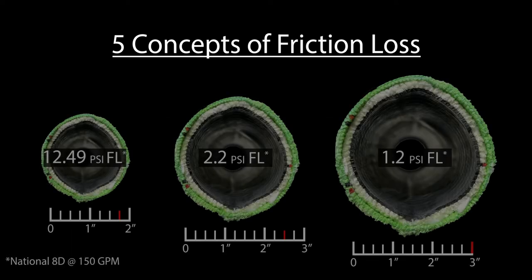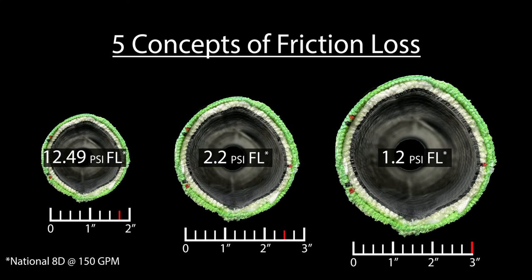Third states that as the diameter of the hose line is increased, the friction loss will decrease drastically. A greater diameter means more space for the water to move, which reduces turbulence in the line.